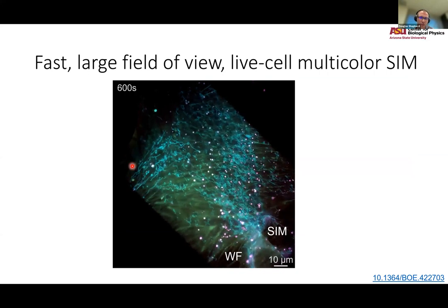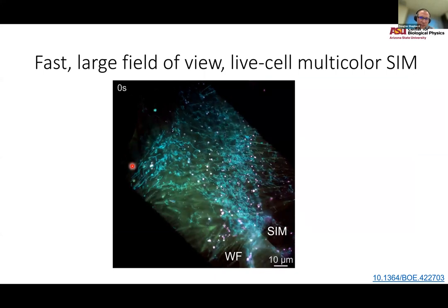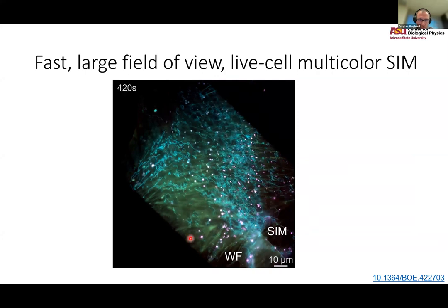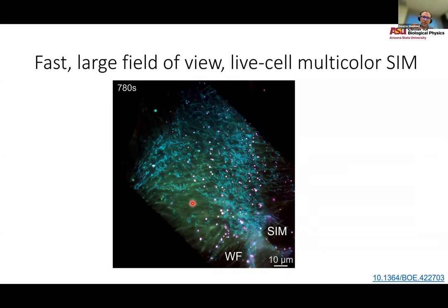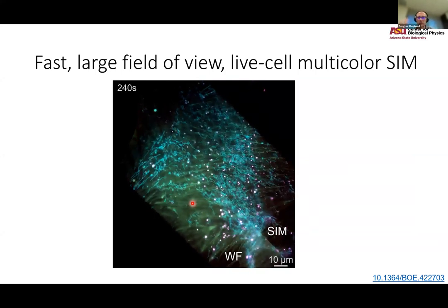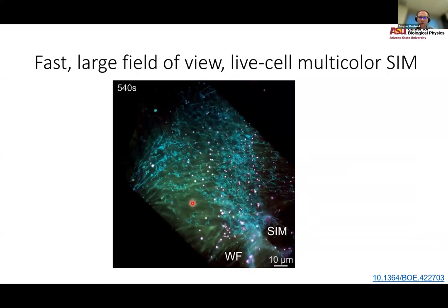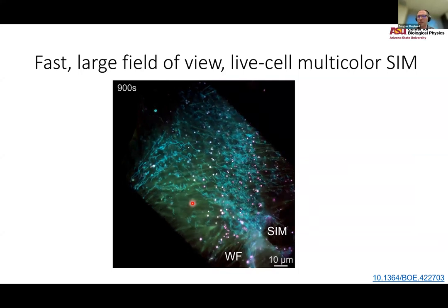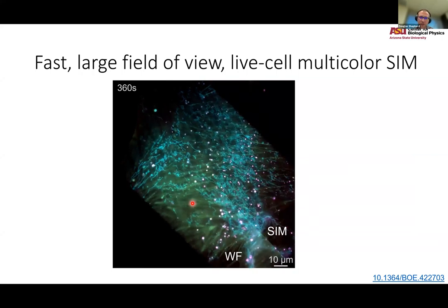So what we're tracking here are mitochondria in cyan, lysosomes in pink, and then the underlying actin cytoskeleton in this greenish color. And the thing I want to point out is it's a bit blurry here. The reason it's blurry is because of this out of focus fluorescence. So it turns out SIM is still really subject to light hitting it from above. And so even though we've improved the transfer function laterally, we really haven't done much axially. So the next step to be able to do those types of experiments we're interested in is, how do we get better axial resolution?